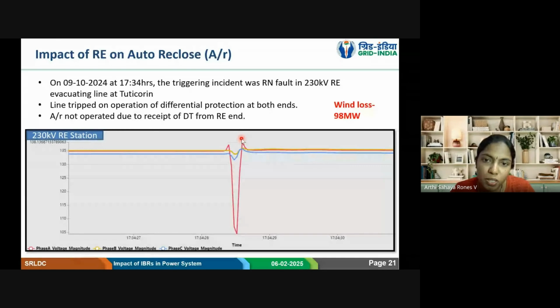So during transient faults, the auto recloser will open and then it will reclose after 1 second. As per the IEEE standard, based on the deionization timing and arc extinction time, 1 second is decided. So that dead time is 1 second. After the 1 second dead time, the breaker will try to reclose. If the fault is persistent, it will lock out. If the fault is not persistent, then the line will be reclosed and normal operation will be resumed. So that is the thing. Whereas in these RE evacuating lines, we are facing this issue. In most cases, auto recloser will not happen properly.